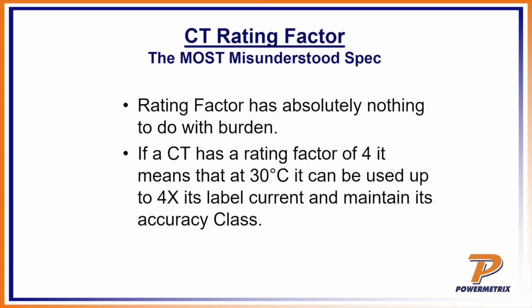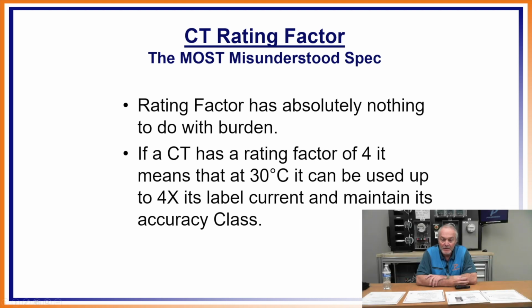CT rating factor, according to Mr. Hudson, is the most misunderstood spec. So the rating factor has absolutely nothing to do with burden. If a CT has a rating factor of 4, it means that at 30 degrees C, it can be used up to 4 times its label current and maintain its accuracy class. Notice Steve put the 30 degrees C.